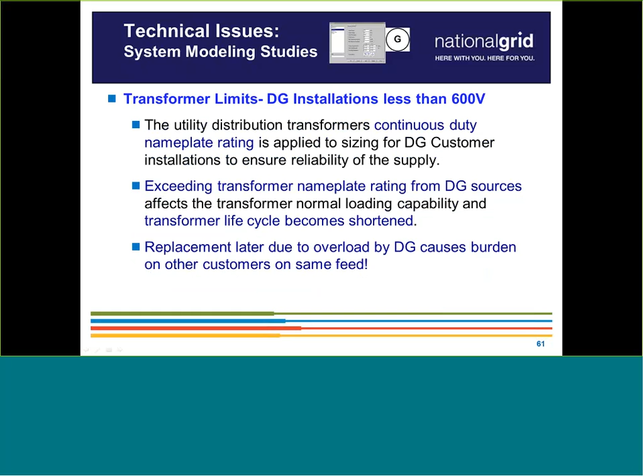All right, so this is sort of touching on those transformer limits that I mentioned earlier. This really goes more along with behind-the-meter customers, simplified applications, that sort of thing, where there's an existing transformer and you're proposing generation that's going to exceed the nameplate rating of that transformer. So that's a situation where we'd have to upgrade that, make sure that there won't be an overload. So you can't put your 600 kilowatt solar system behind our 500 kVA pad mount transformer. So we'd have to upgrade it, make it a 750, something like that.